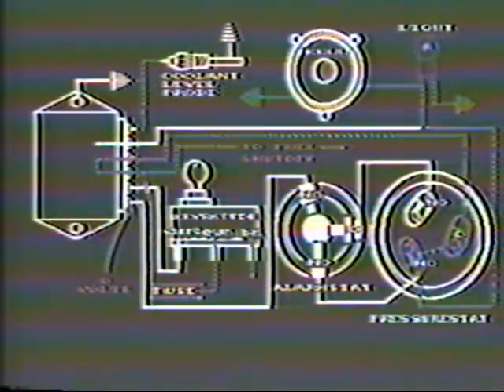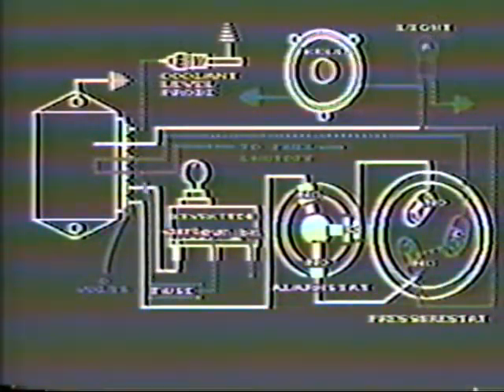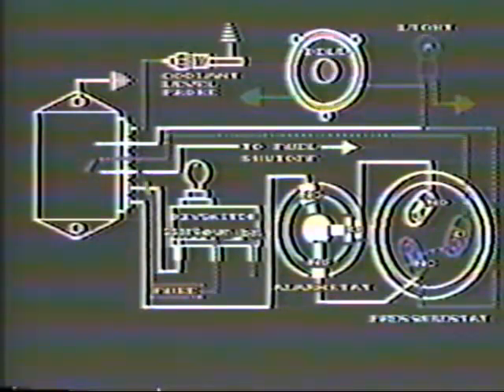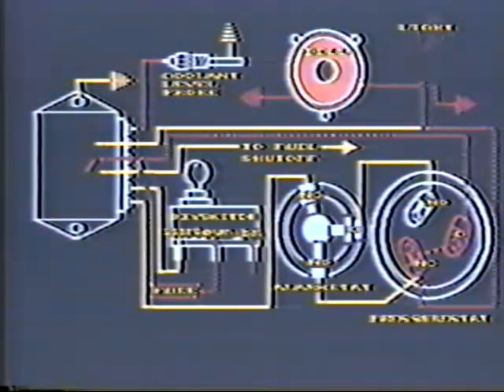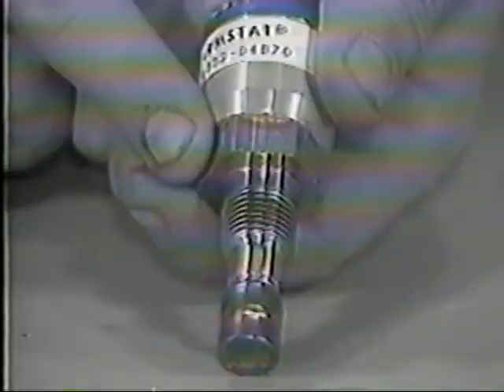If oil pressure continues to fall, the pressure stat NO switch will open at 10 pounds. This removes voltage from module terminal 1. As voltage vanishes from terminal 1, the module instantly opens the run switch, disconnecting voltage from the fuel shutoff and causing a shutdown. The process is similar if the engine should overheat.